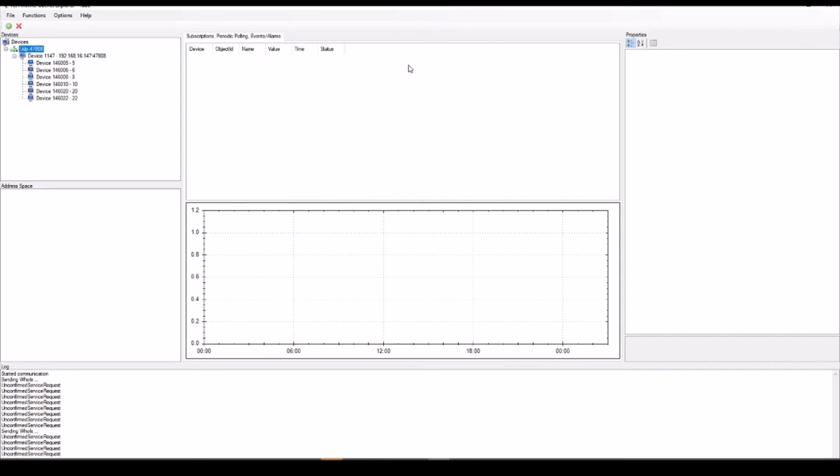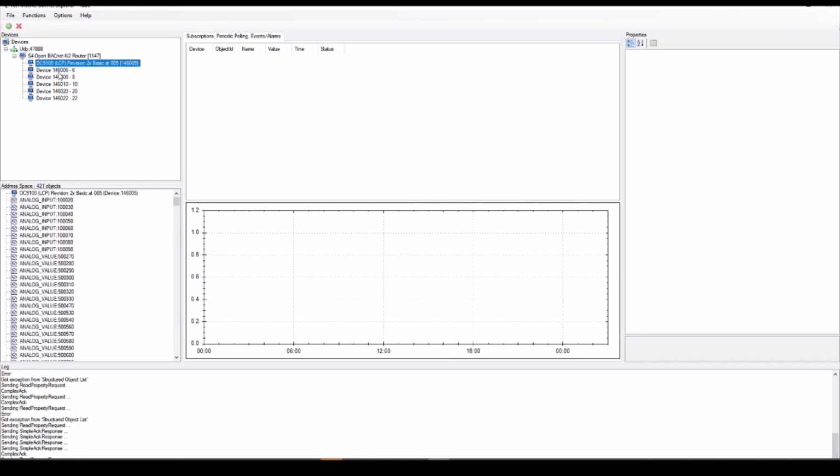This represents an important step in the integration process, verification that you are receiving the expected data through BACnet. Next, we will ask it to provide details for the N2 router itself and each of the 6 emulated BACnet IP devices representing the legacy N2 devices that we just integrated. And that's as simple as just touching each device and its properties will get expanded.